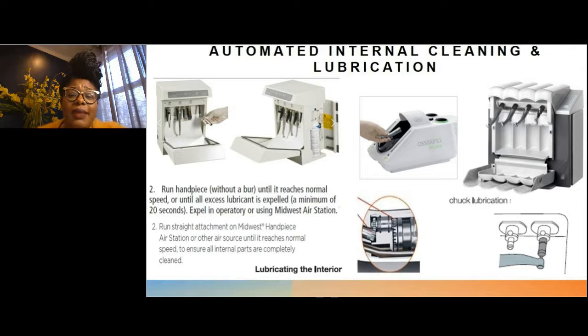So there's also automated internal cleaning and lubrication. This can happen with a machine, or you can have it be done manually as well. So here is an excerpt from an IFU where it is telling you to run the handpiece until it reaches a normal speed, or until all excess lubricant is expelled, at a minimum of 20 seconds. Expel in the operatory or using one of these automated systems here. The whole purpose of this is to actually get lubrication into the inner workings of your handpiece. You want your handpiece to be fully functioning. You don't want your handpieces to be jamming up.